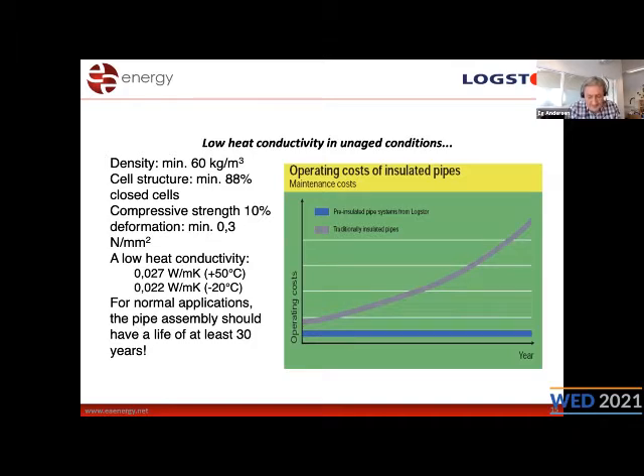Now that diffusion barrier is a technology that Logstor has worked very hard on, to find a way to prevent the insulation value from escaping out of the plastic jacket. With traditional insulation or other kinds of PE materials used as an insulator, they could be very well insulating to begin with, but over 5 years they will lose a lot. Up to 60% of the insulation value will disappear through the jacket. But since Logstor has this diffusion barrier of aluminum, for example, you will not see the energy disappear. So you will have the same quality throughout the expected lifetime of the pipe system, say 50 years.